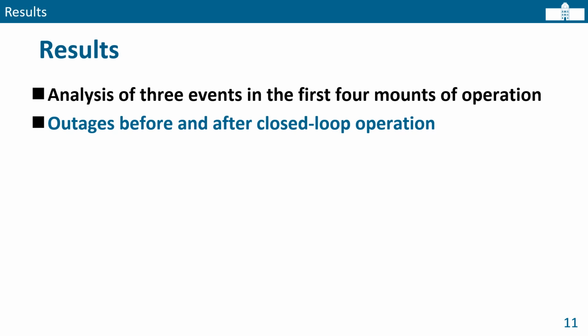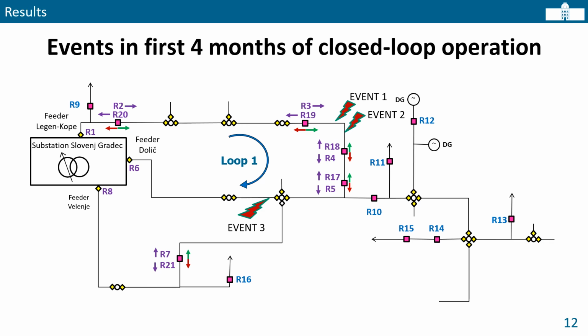Results are given for the first 4 months of operation, and an additional analysis of outages before and after the introduction of closed loop operation is performed. So during the first 4 months of closed loop operation, we had 3 events. 2 events were just one span apart, and event number 3 occurred during maintenance work, where it came to a 3-phase short circuit.